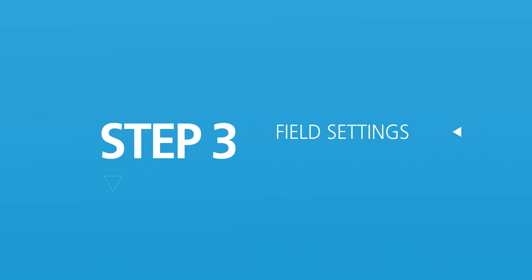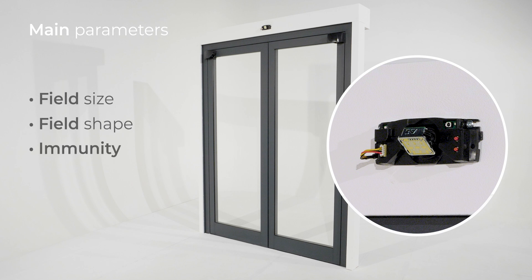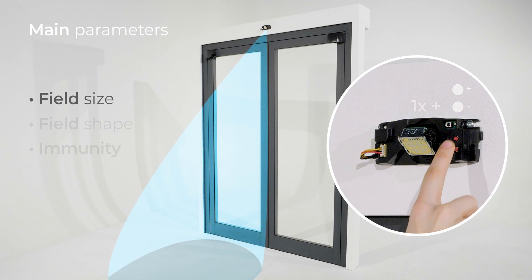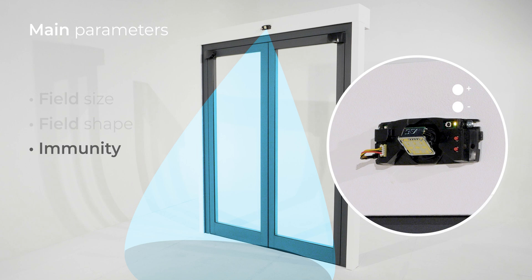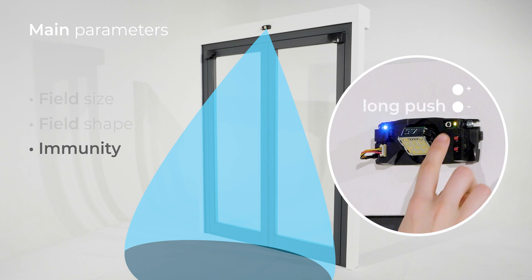Step 3: field settings. Adjustment of the three main parameters is possible by push buttons: field size, field shape, and immunity. To adjust the size of the field, push minus to decrease the size and plus to increase it. To adapt the field shape, a long push on the minus button enters the menu — the right LED turns blue — then use plus and minus to change from a narrow to a wide field; a long push on the minus button exits the menu. To adapt the immunity filter, a long push on the plus button enters the menu — the right LED turns yellow — then use plus and minus to adjust it; a long push on the plus button exits the menu.